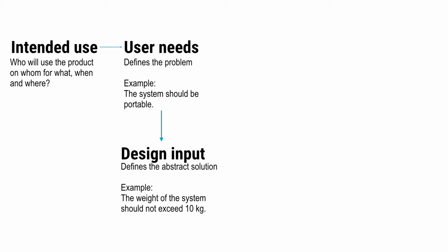The regulatory requirements do not say who should come up with user needs and design inputs, but many times the people who are competent to define user needs are found in the marketing department or typically work with product management. Since the design inputs should be technical in their nature, they are usually established by engineering and should use engineering language.